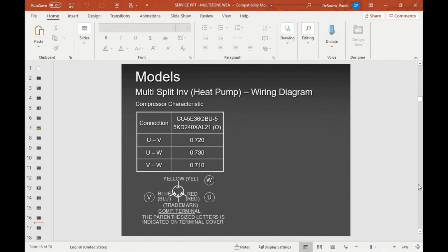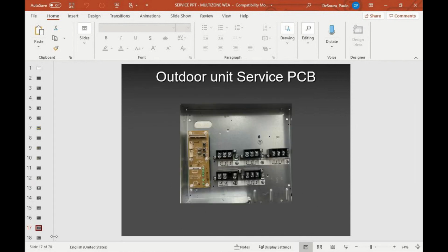Okay? So if you have a sensor that you think is defective, in our service manual or on our app that I mentioned earlier, the Panasonic Air Conditioner Quick Service Guide app, you will see how to get the values. All our sensors are in kilo ohms, 5 kilo ohms, 10 kilo ohms, 200, you name it, depending on what sensor you're looking at. Some guy will tell me, Paul, why do you say the compressor is defective when I'm reading the correct resistance between UV, VW, WU, WV? Well, the answer is the coil is good, but the compressor is seized, mechanically damaged.